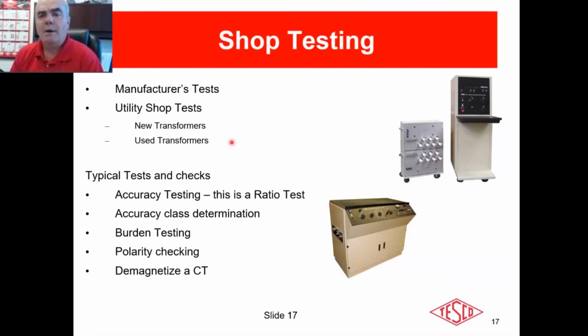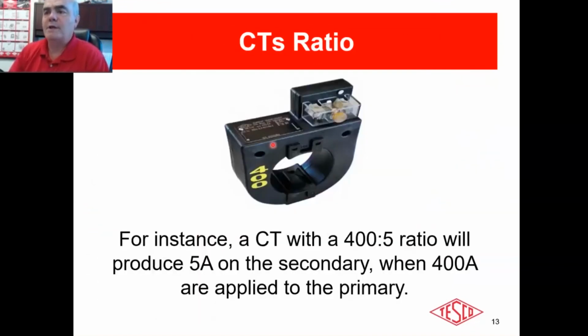Okay, so typical tests. What are we going to test when we test a transformer? Well, we'll do an accuracy test. That's really just a ratio test, all right? And that's going to give us our accuracy class determination. We're going to do a burden test because we want to see how that transformer operates over a variety of burdens. We're going to do a polarity check. Well, what's a polarity check? If you remember over here, see that little white dot there? That marks the polarity. That tells you how that transformer should be set up, all right?